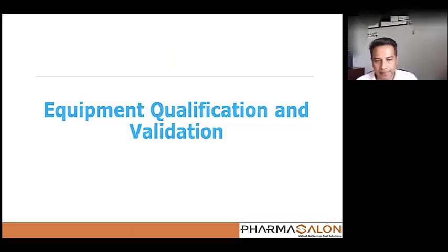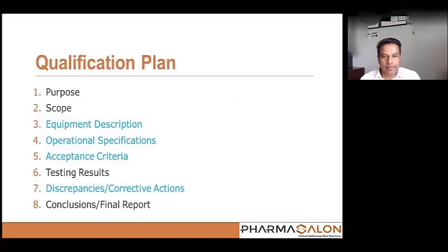equipment qualification and validation. The equipment used at the facility must be qualified and validated prior to use. For an equipment to be qualified, there should be a plan covering the purpose, the scope, the equipment description, operational specifications, acceptance criteria, testing results, discrepancies or corrective actions, conclusions, and the final report. So anytime we purchase an equipment, there needs to be a clearly defined purpose for it.